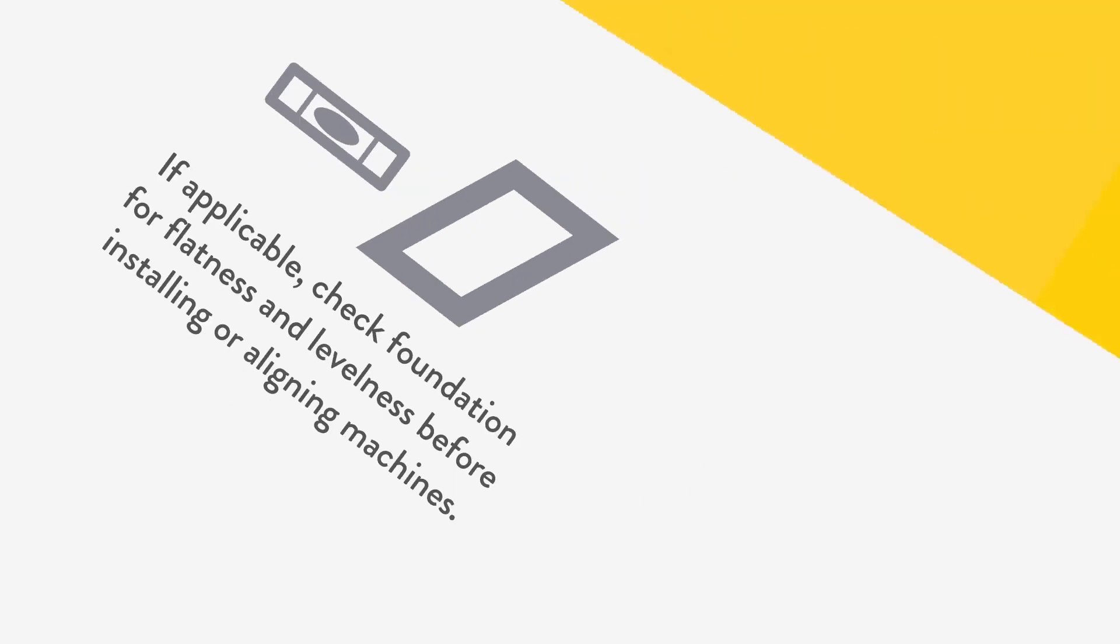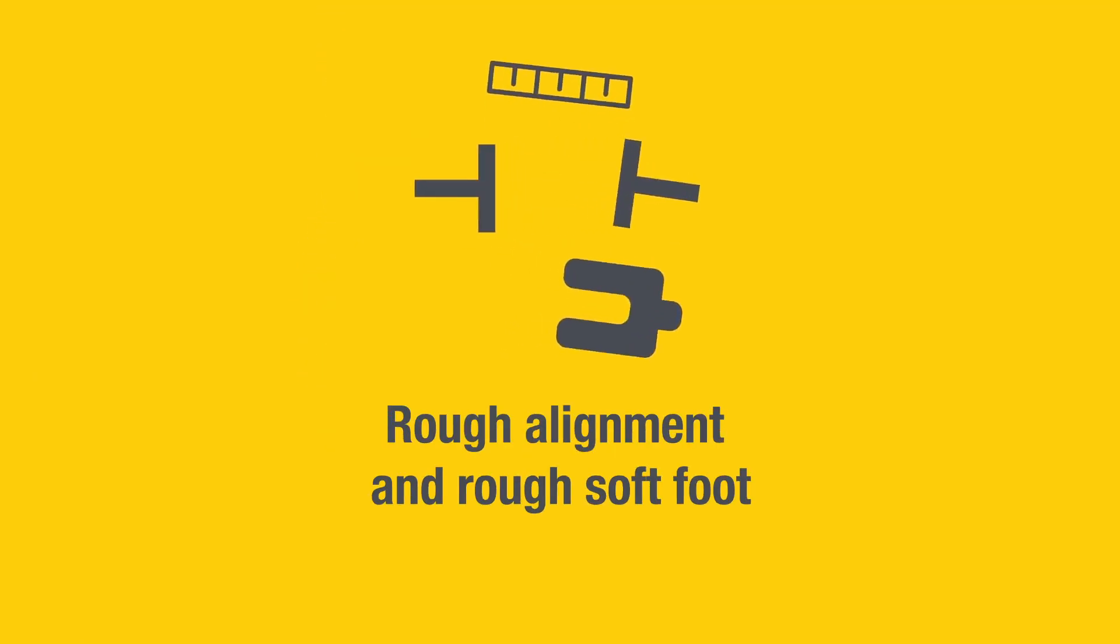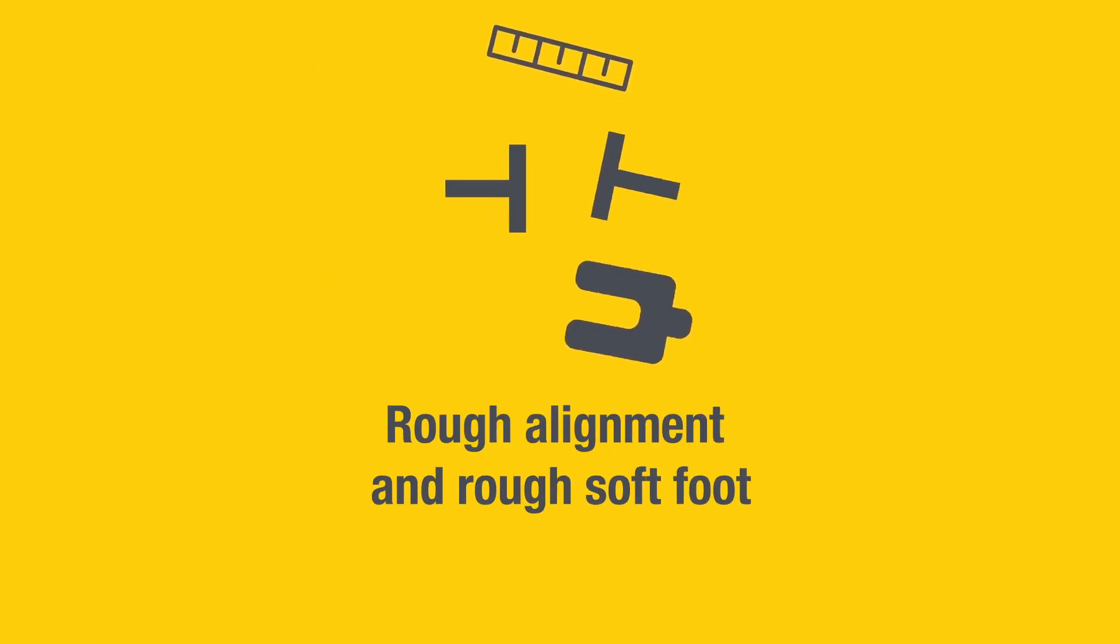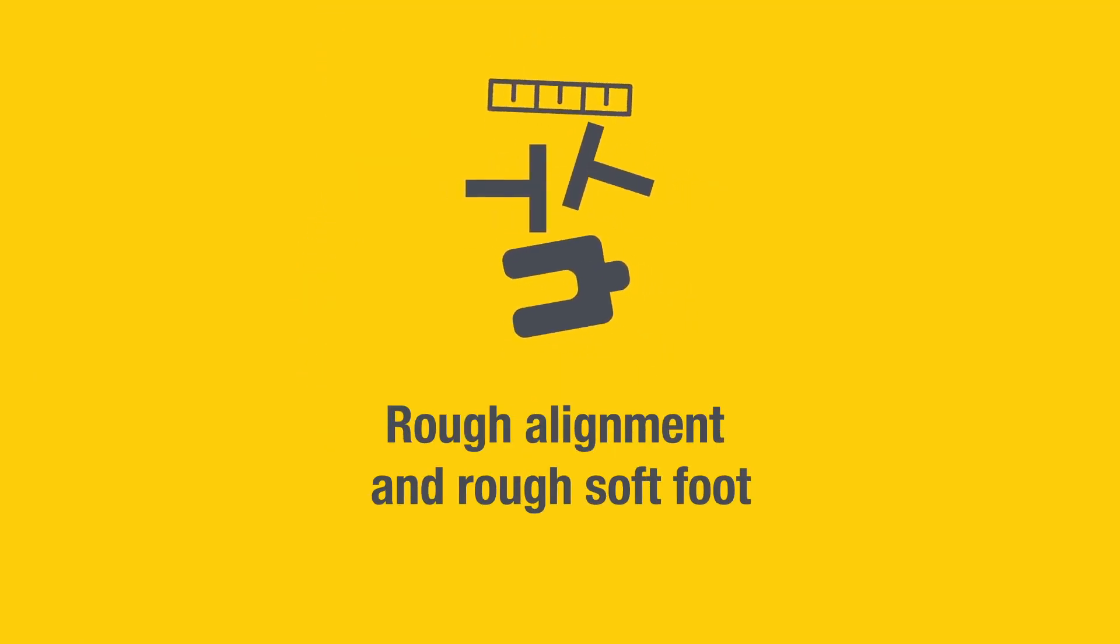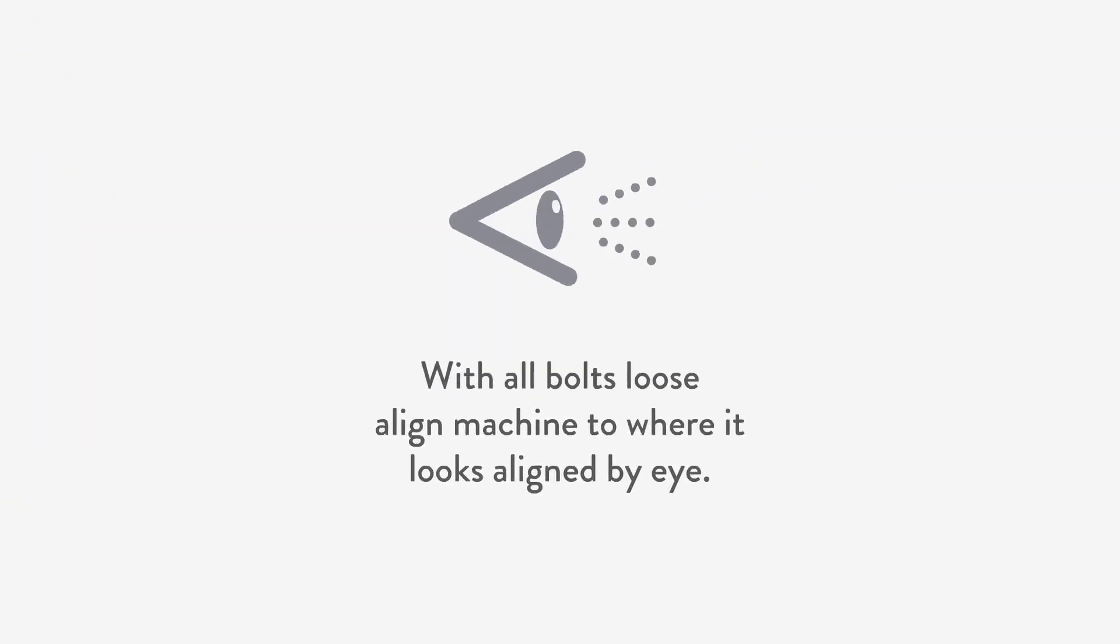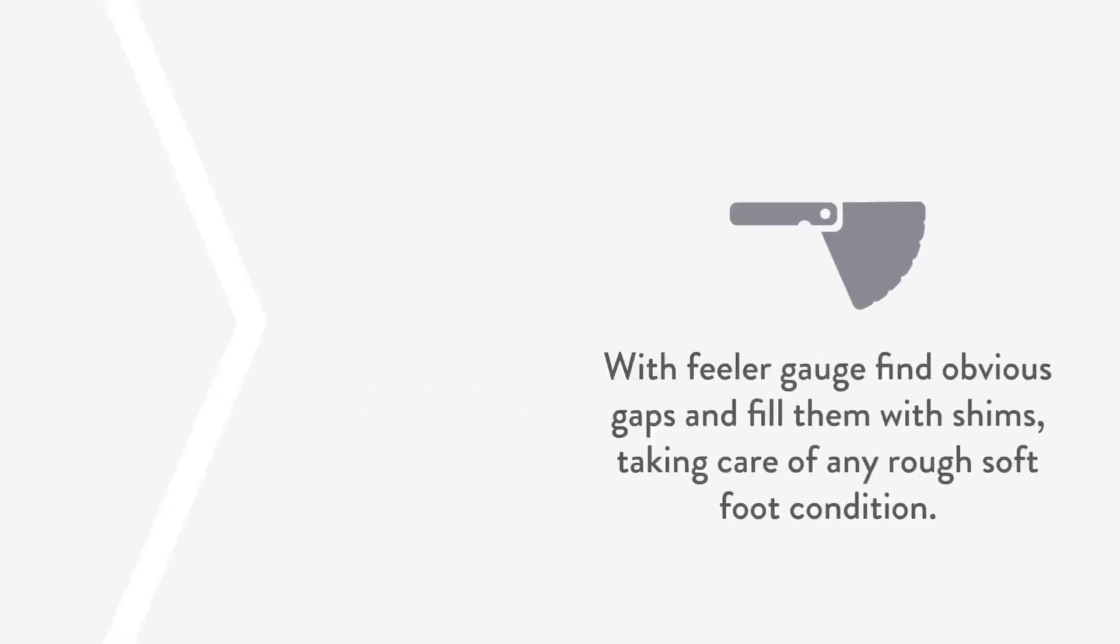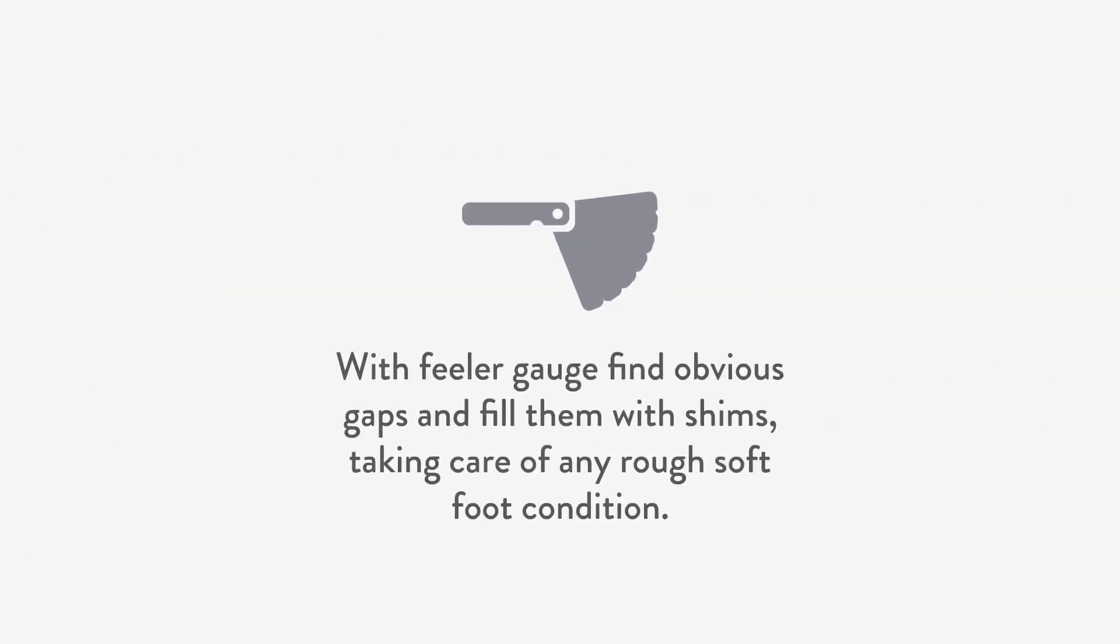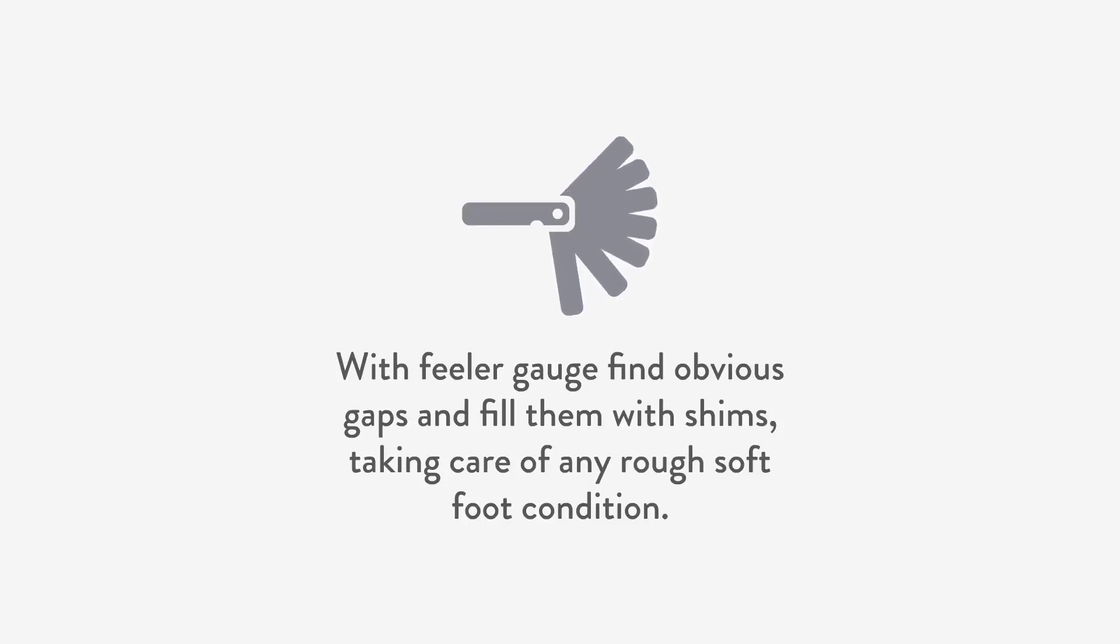Secondly, we perform a rough alignment and rough soft foot correction simultaneously. With all bolts loose, align machine to where it looks aligned by eye. With feeler gauge, find obvious gaps and fill them with shims, taking care of any rough soft foot condition.